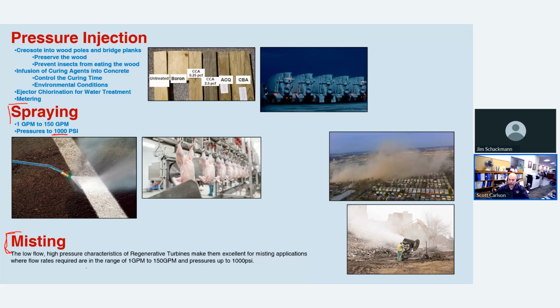For misting, when you're at a construction site, and there's a lot of dust, especially if it's demolition or waste or any kind of waste management service that is going to have a lot of dust naturally occur. They have these fans that are manufactured that have water lines with nozzles on the end of them, and you would use a regenerative turbine pump to push fluid through those nozzles to make a fine mist that blows out over the air, mixes with the dust particles that are in the air, grabs them and pulls them down to the ground. So you can control dust using these misters.